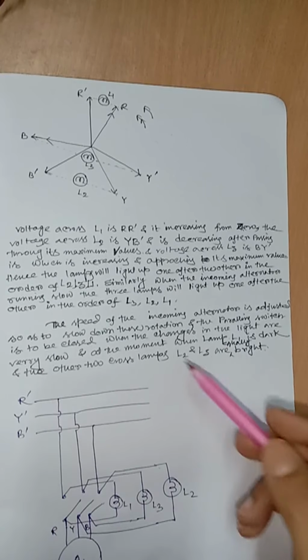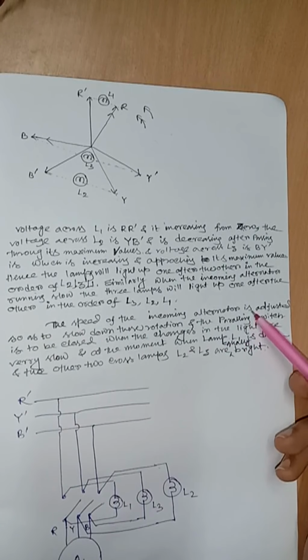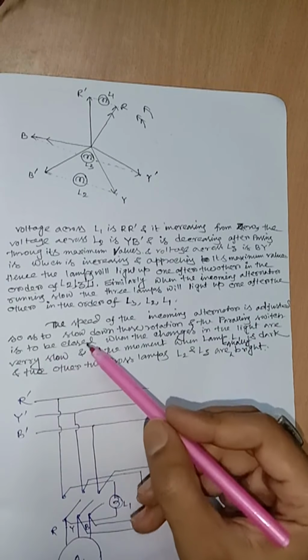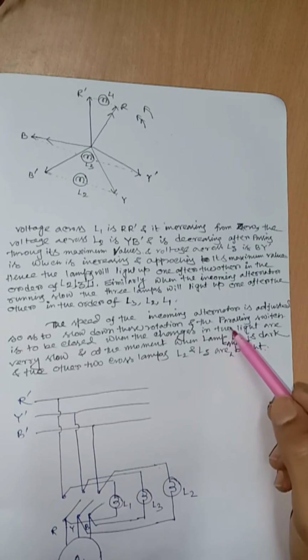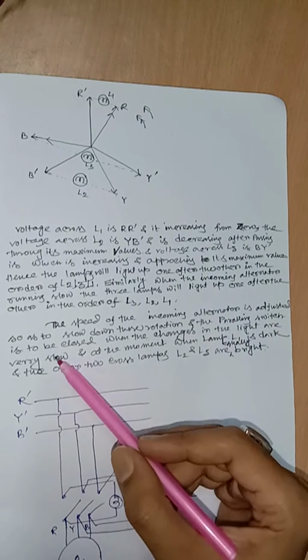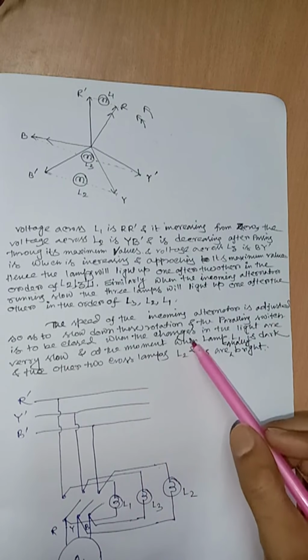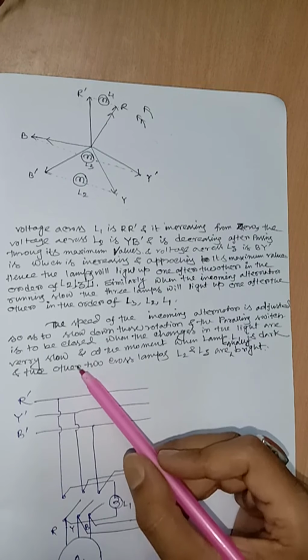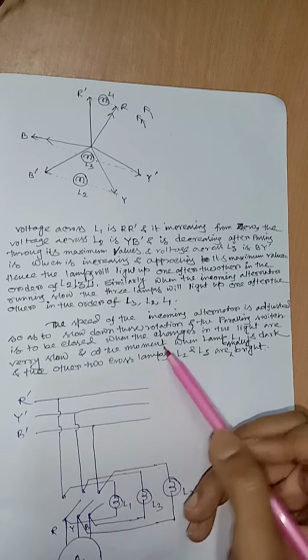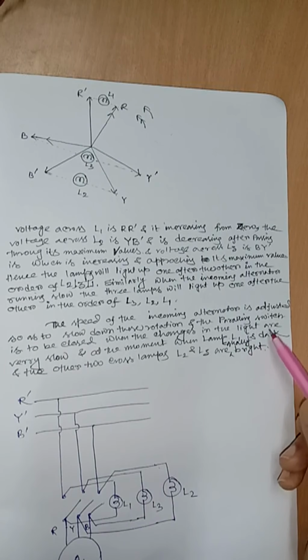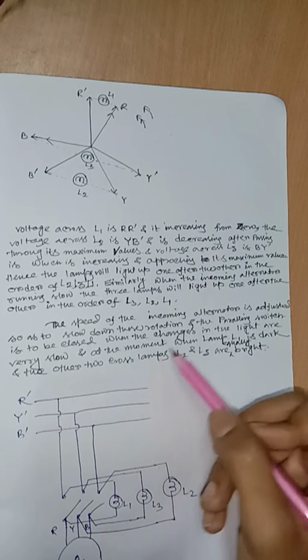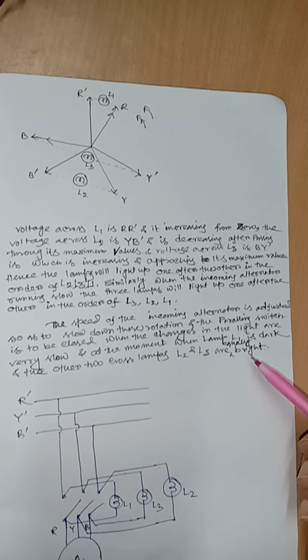The speed of the incoming alternator is adjusted so as to slow down this rotation, and the paralleling switch is to be closed when the changes in the light are very slow, and at the moment when lamp 1 is dark and the other two cross lamps L2 and L3 are equally bright. So this is our two bright and one dark lamp method. Later we will discuss the synchroscope method. So thank you.